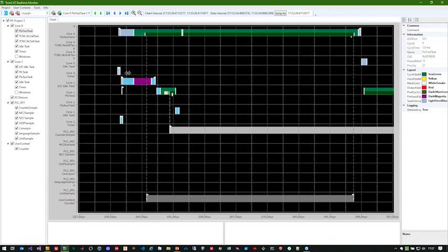This is all done by the IO idle task, and this means as soon as you measure something with the real-time monitor, you will change the real-time behavior, and that's why it does not make sense to have the IO idle task at a higher priority than the PLC task. There are only a few cases when it makes sense that the IO idle task has a higher priority than the other real-time tasks. So this is also something you may want to change afterwards.